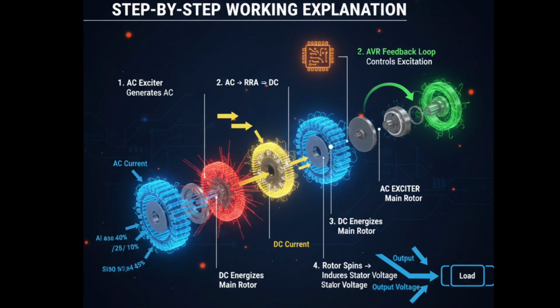Step 1. The AC exciter mounted on the alternator shaft generates alternating current as the shaft rotates. This AC voltage is proportional to the speed of the shaft, and the exciter is mechanically coupled to the main rotor. Step 2. The generated AC flows into the rotating rectifier assembly, which converts it to direct current. The diode bridges in the RRA are highlighted on the slide in glowing orange, showing how they rectify the AC into pulsating DC.